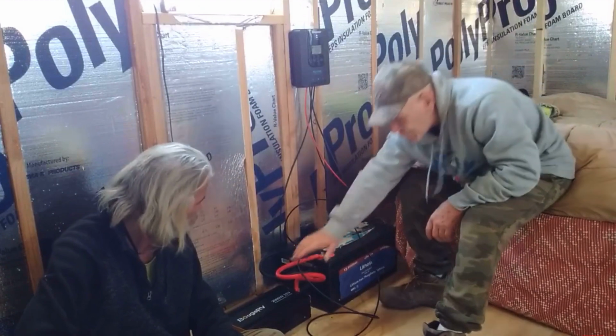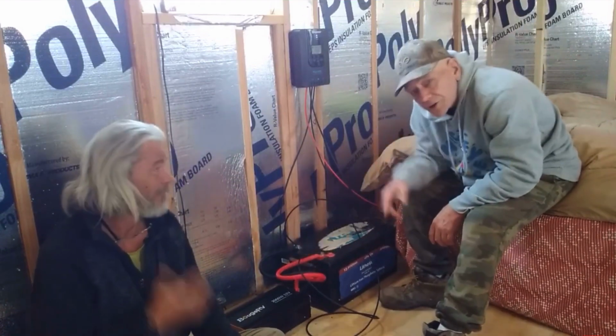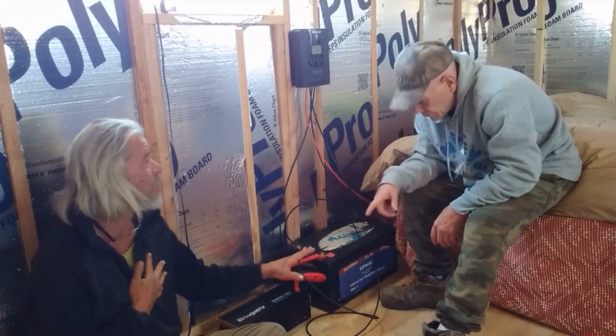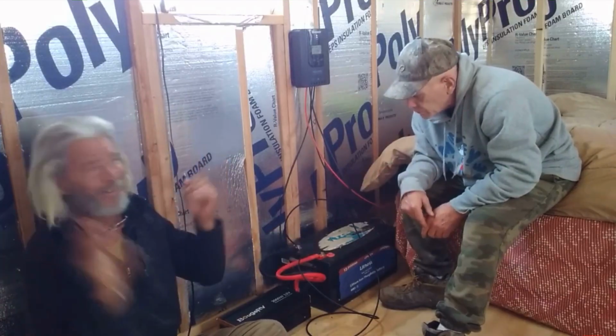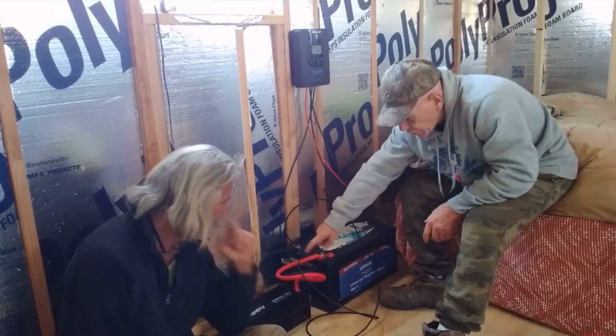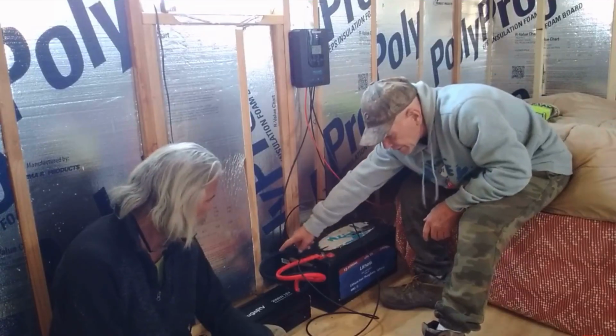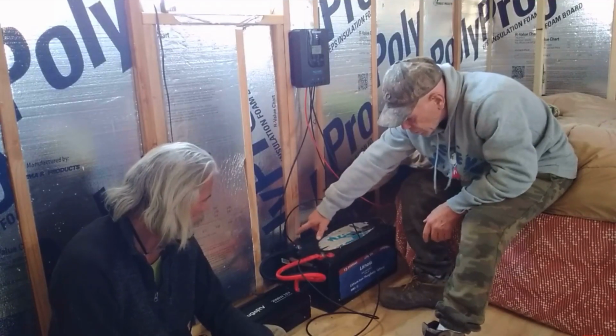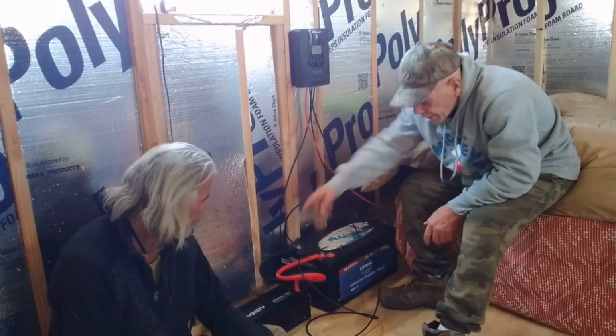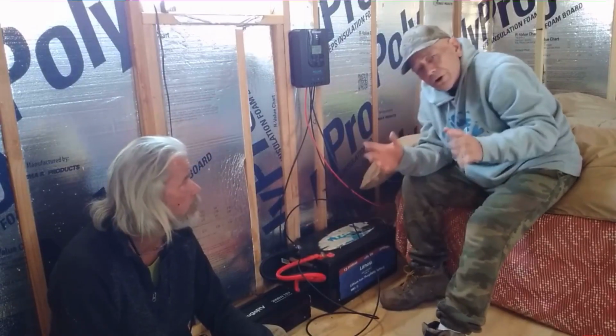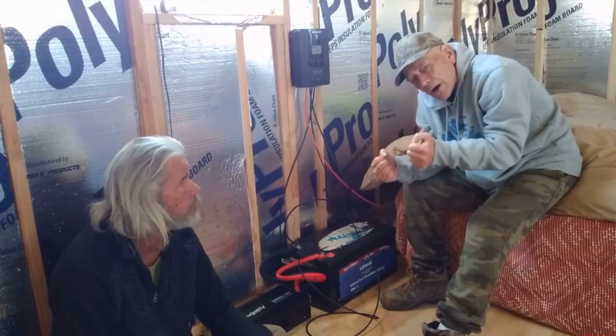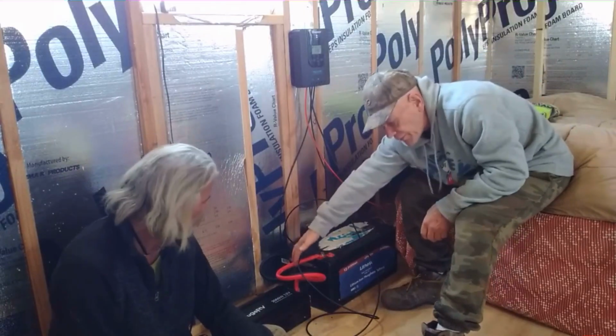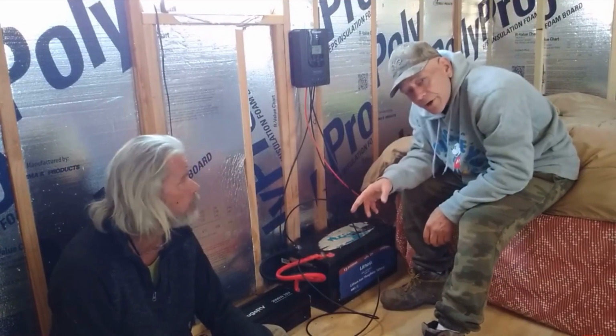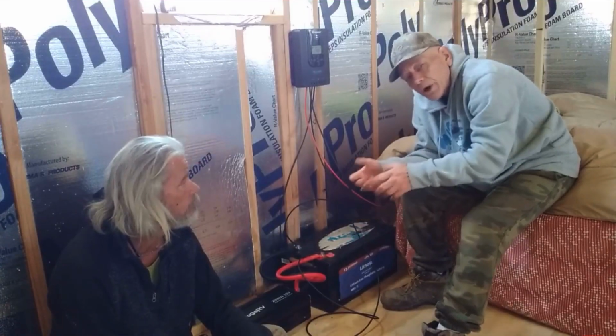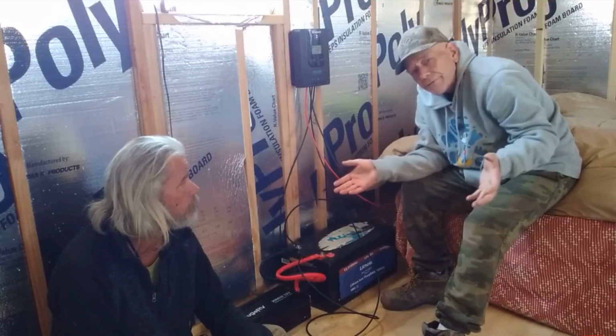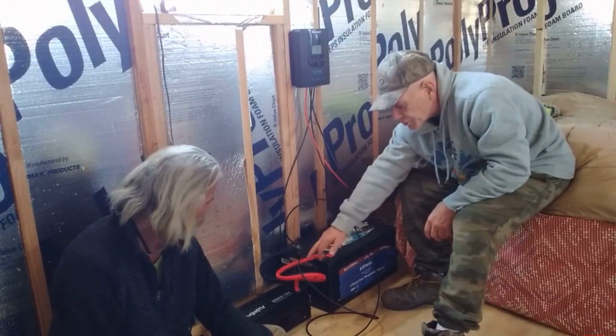Now notice we've got heavy duty wiring. It's important that you match up your wiring - that was my biggest confusion when you and I were talking, I was so confused. The wiring we're using here is very heavy, like 2 gauge wire, maybe even 1 gauge, but I believe it's 2 gauge. The reason is when the inverter kicks on, it has to pull a lot of power through that wire. If you don't have large enough wires of the proper gauge for an inverter, it can cause the wires to overheat, possibly burn out, or it will kick off the inverter so it won't work. So it's important that you match up your wiring.